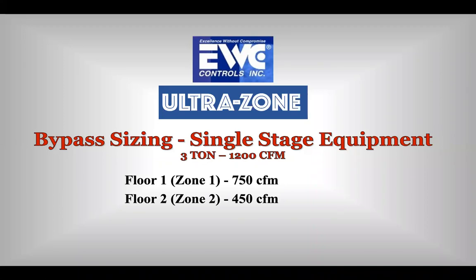scenario. Worst case scenario would be when I'm shutting off the extreme or the most airflow during operation. This would easily be detectable: we're going to get a call in floor 2, zone 2, 450 CFM, and I've got to have a way to accommodate the additional 750 CFM.